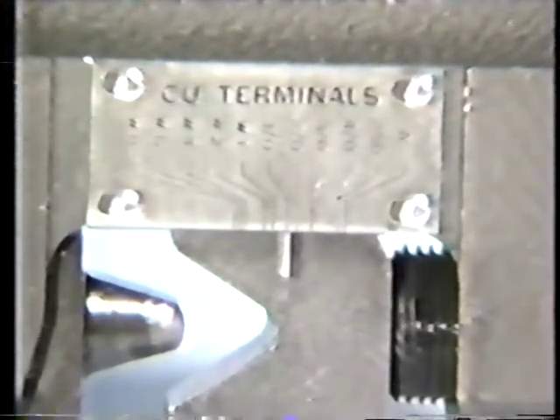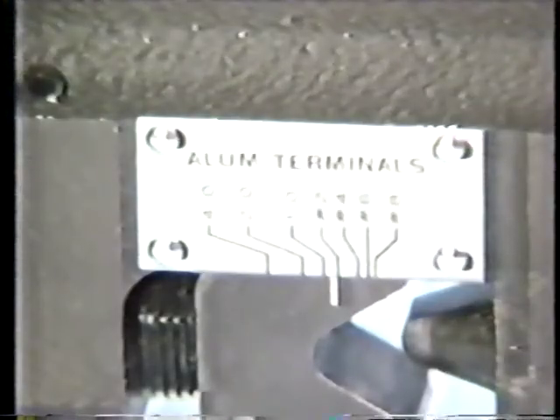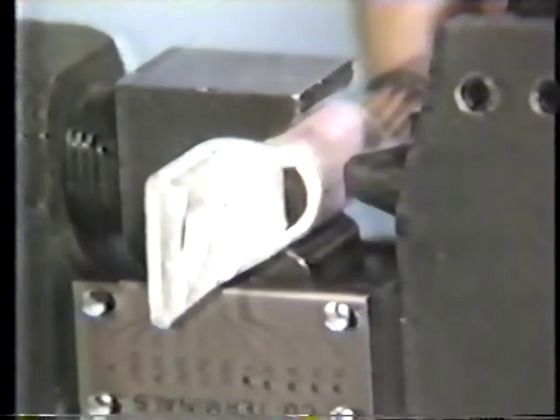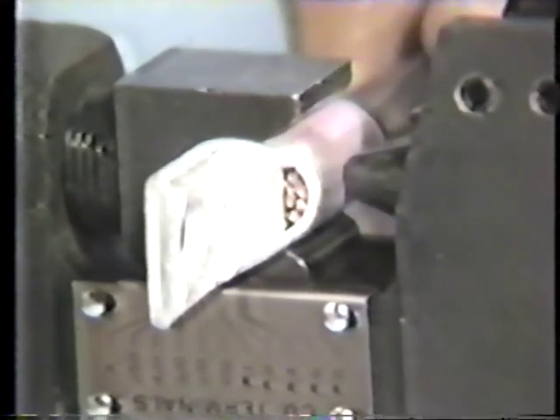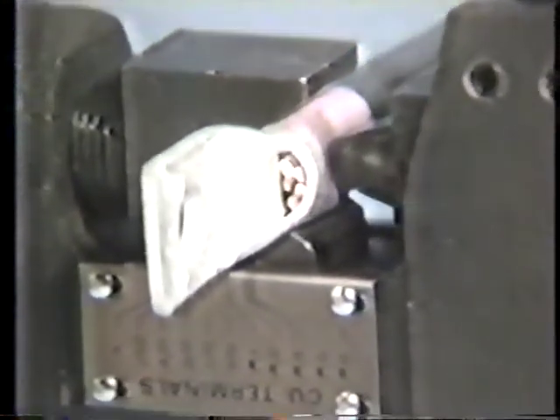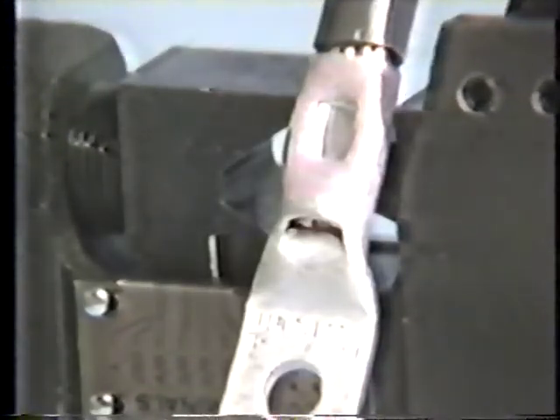Please note that copper conductor settings are shown on one side of the tool, while aluminum settings are shown on the opposite side. With the tool set to the proper conductor size, place the compression terminal into the die. Insert the conductor fully into the terminal and crimp directly on the colored bands. Although Burndy terminals can be crimped anywhere around the barrel, we recommend that the crimp be perpendicular to the tongue for a more professional appearance.